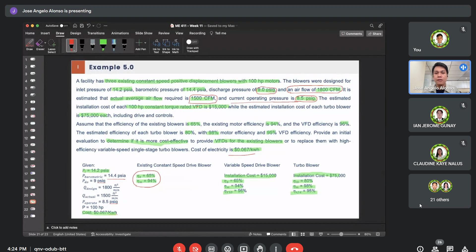Next is to estimate the variable speed drive blower power consumption. Same equation, we will use the isentropic work equation. However, what we will change here is the volume flow rate or the blower capacity. As I said earlier, the actual average flow required is just 1,500 CFM, meaning there's a reduction of 300 CFM once we install a VFD.